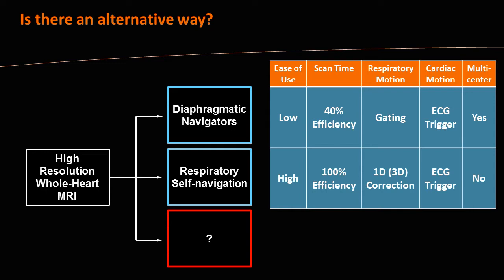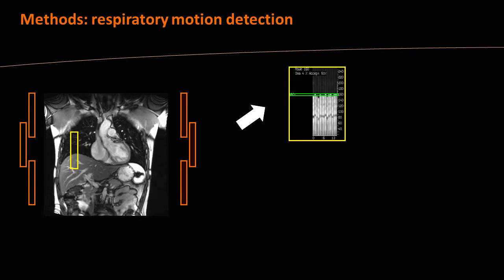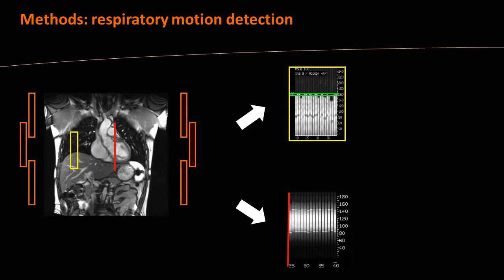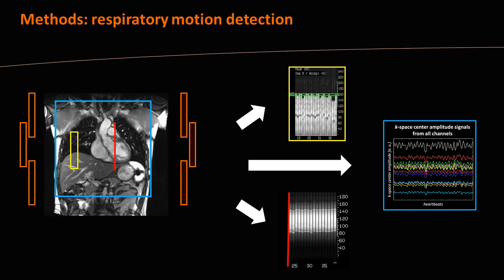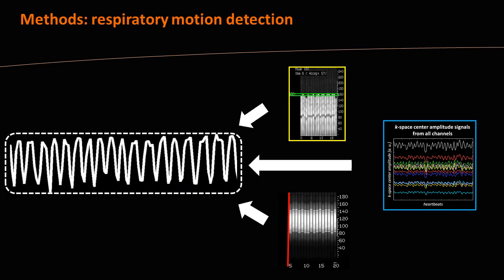Is there an alternative way to do high-resolution whole-heart coronary MRI? The core concept is that we always have to detect respiratory motion whether we gate or correct. We can use the navigator as before, use self-navigation directly from the data, or use a simpler method by looking at the intensity over time across all coils — extracting a respiratory signal from FID navigators, i.e., the k-space center amplitude fluctuation of the channels. In this work we use the k-space center, but any of these methods gives a usable respiratory signal.